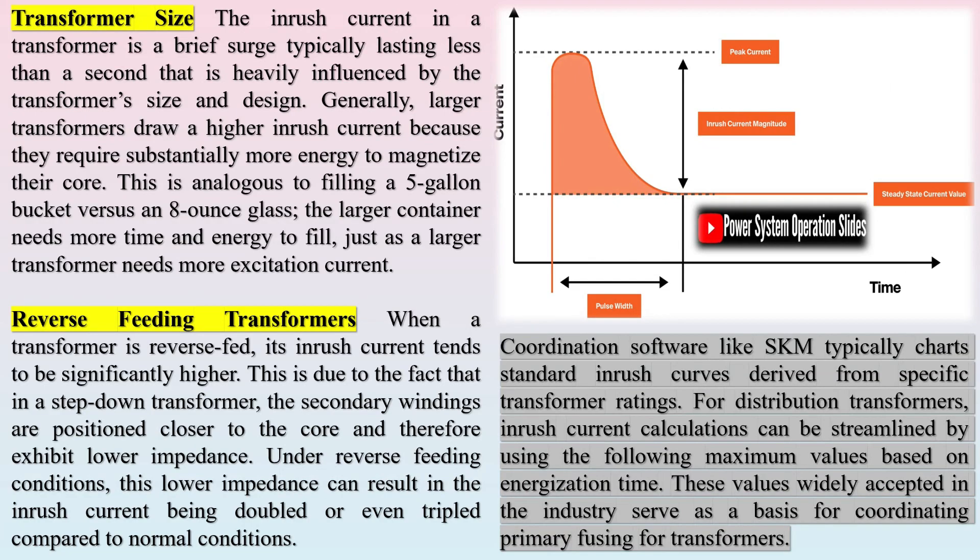Transformer inrush current is the surge of energy required to magnetize the core when the transformer is first energized. This initial burst of current is usually several times higher than the transformer's normal operating current, and its magnitude depends on both the design of the core and any residual magnetism present.